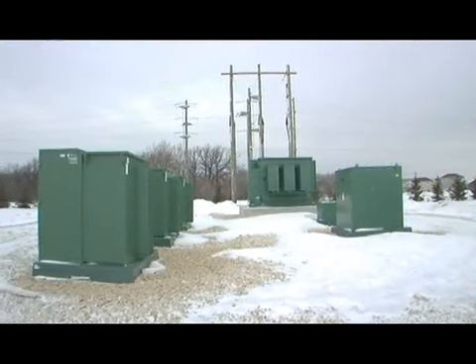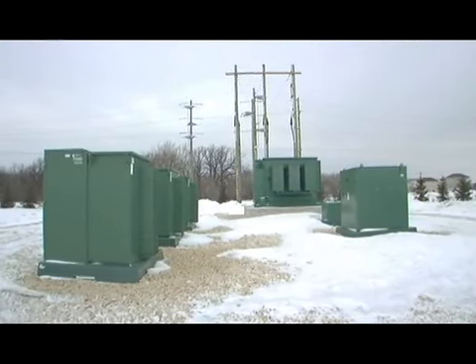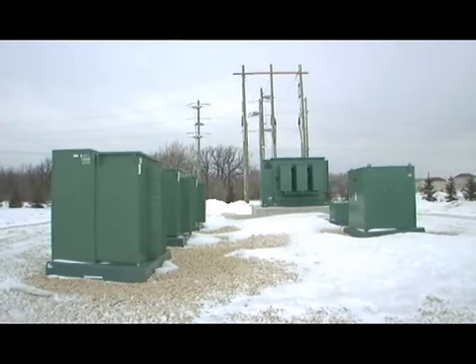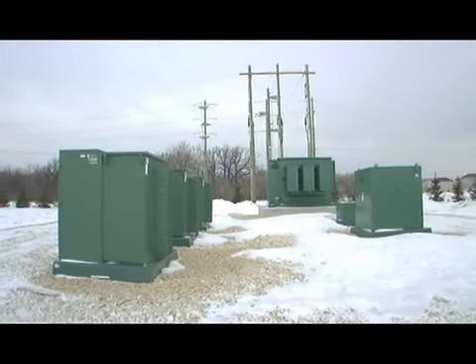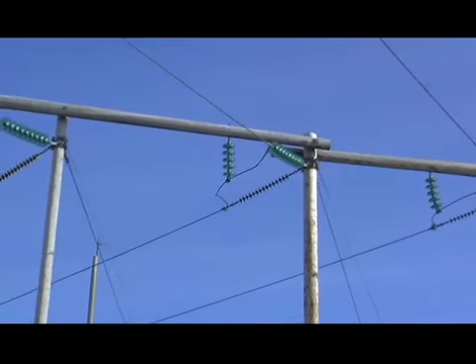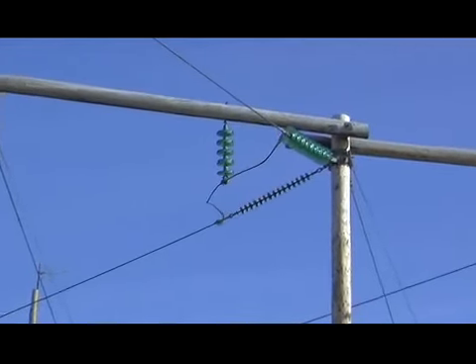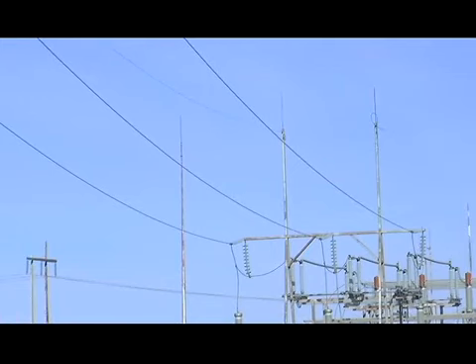The small footprint of the high-voltage pad mount allows it to be placed very close to the load, resulting in extremely short feeders. One of the other advantages to being able to locate these installations close to the load, rather than building 30 or 40 kilometers of distribution line, if the 66 is reasonably close to the load that you have to serve, we can drop one of these things close to the load. Our feeder length has now dropped from 30, 40 kilometers to 5, 6 kilometers, and so we're able to use smaller conductors, we're able to use smaller cables, and it reduces our line losses.